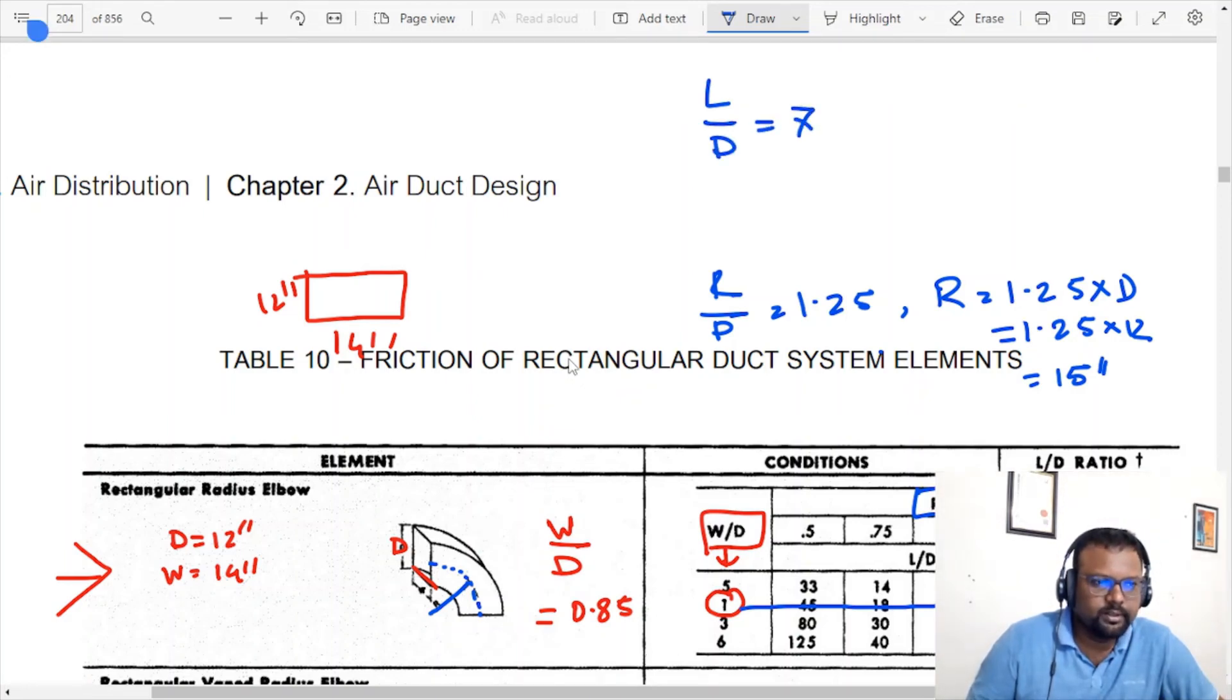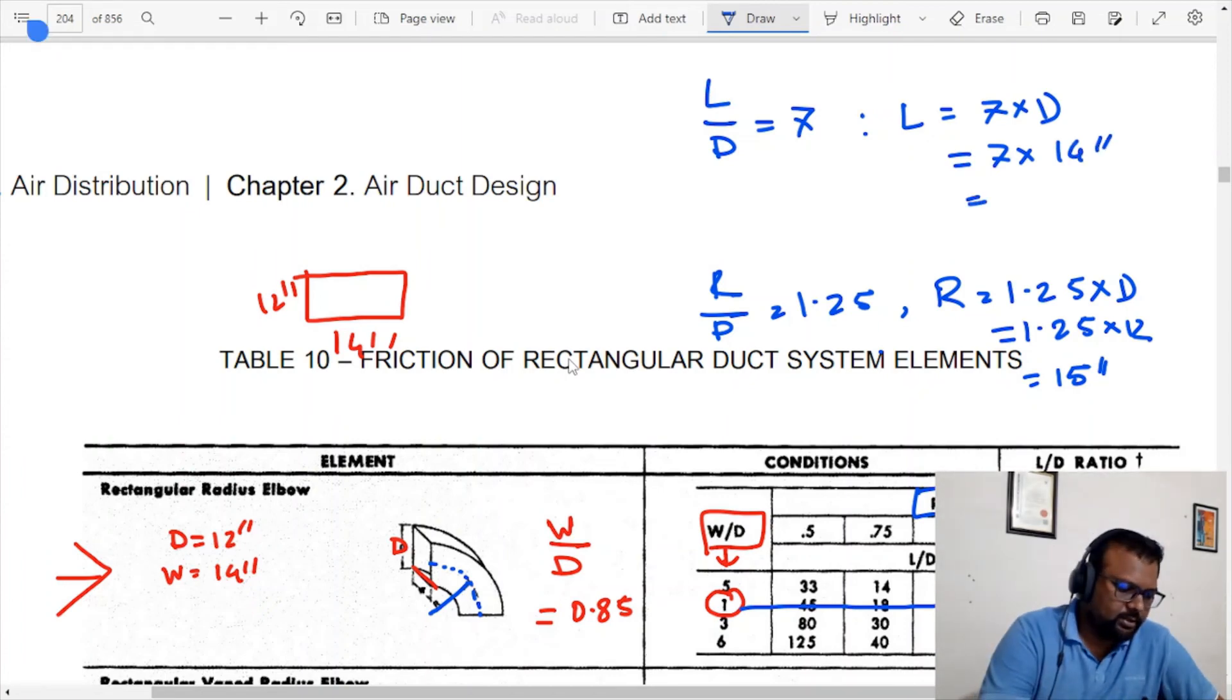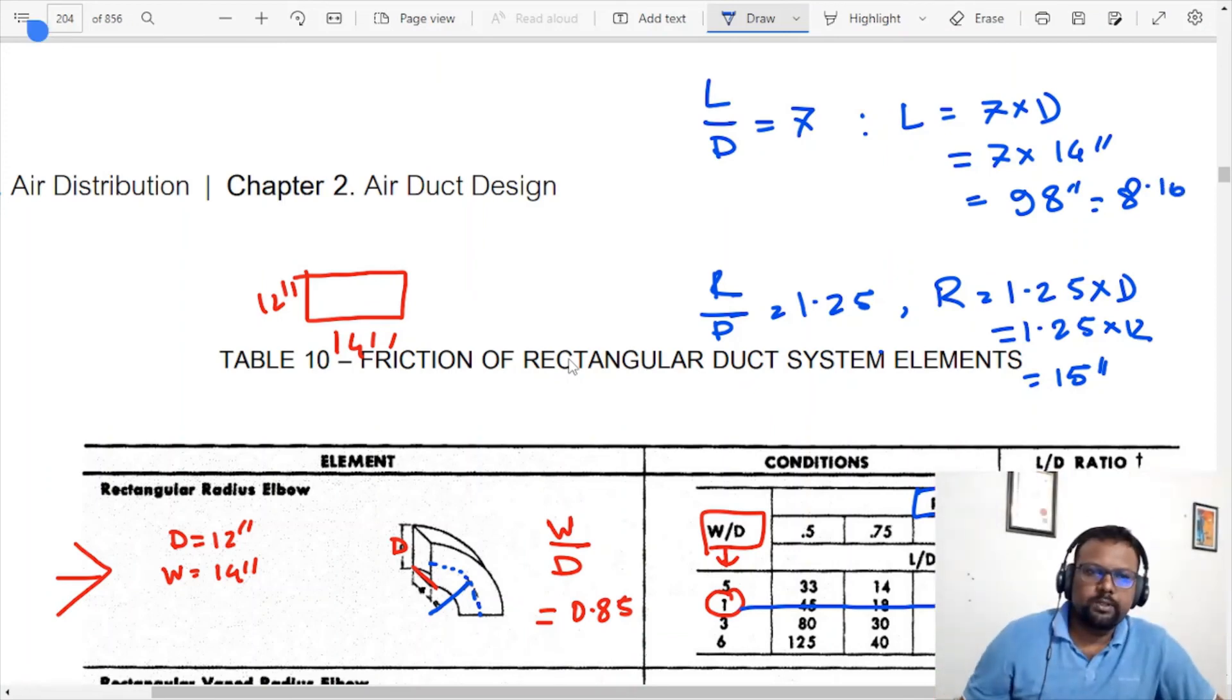Equivalent L equals 7 into D. 7 into D, which is 14 inches, so 7 into 14 equals 98 inches. Converting to feet, that's 8.16 feet. This is how you find it for a straight duct.